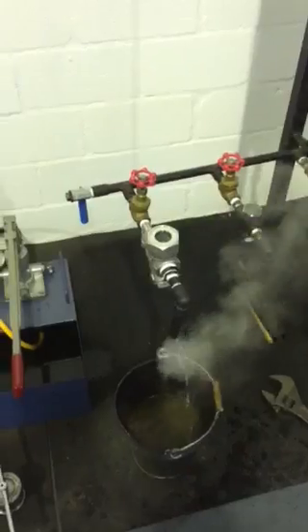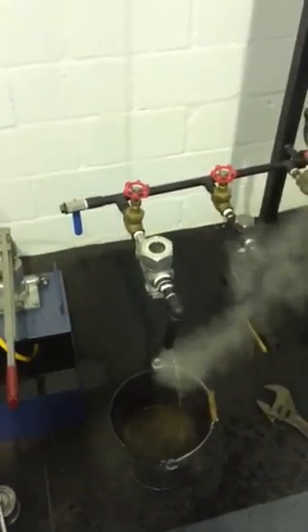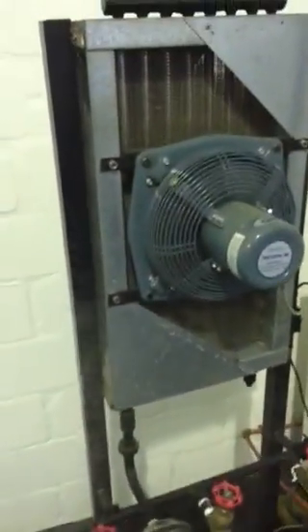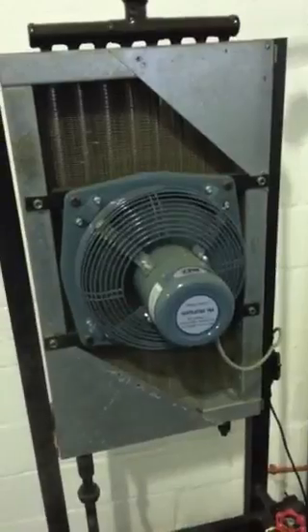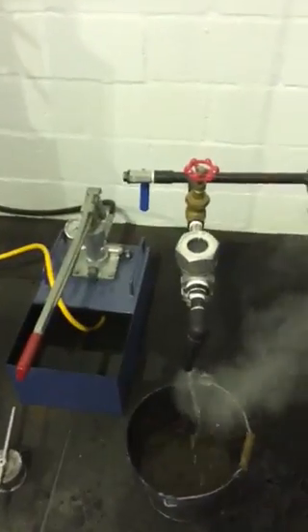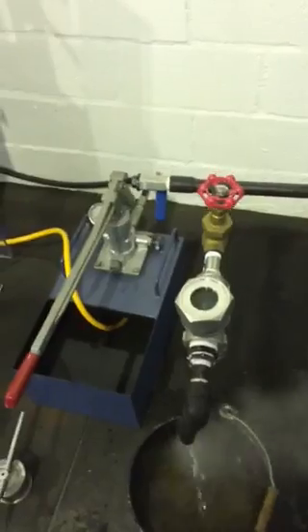Here we have another test with a Venturi Orifice steam trap, but this time the trap has a window cut into the top of it. The fan is running and the system is still at just over three bars, near four bar, and the trap is discharging as it was before.